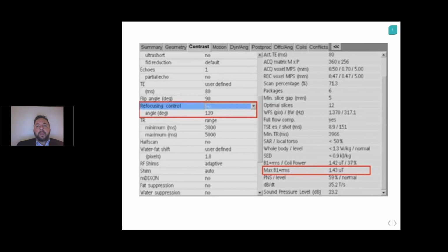So you're seeing a transition in current modern day systems from not only just the recording of SAR, accumulating SAR to two lines below that, the SED, where it's the accumulated dose over sequencing, but then also adding that last and final piece, the B1+RMS, so that we can ensure compatibility with implanted devices and the safety in our patients.